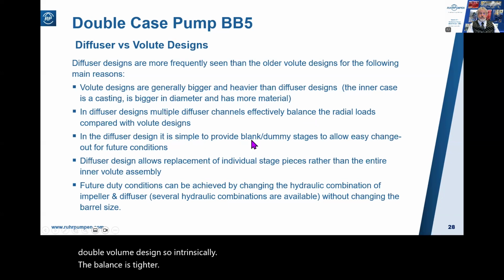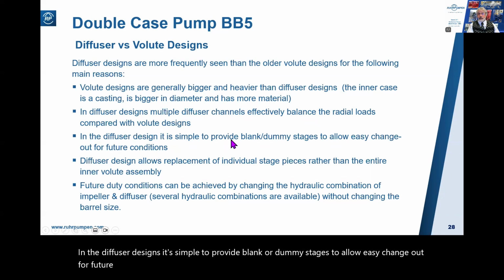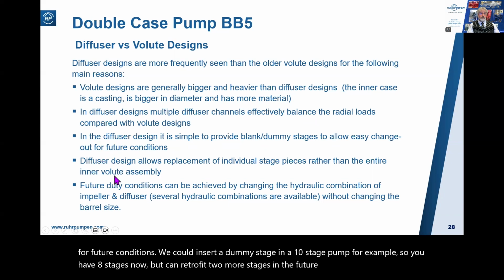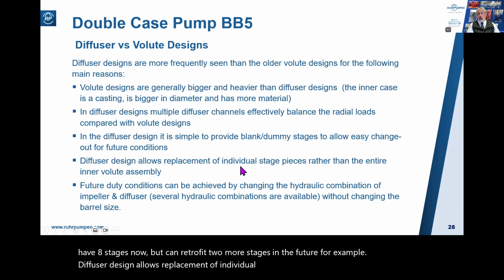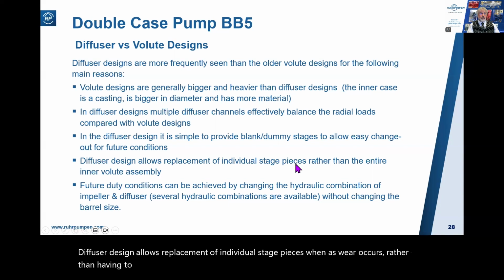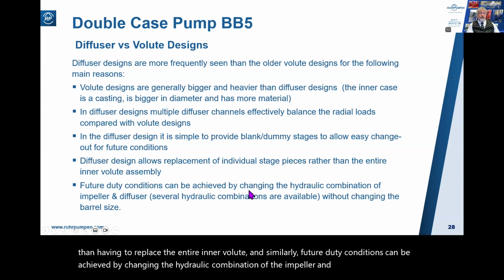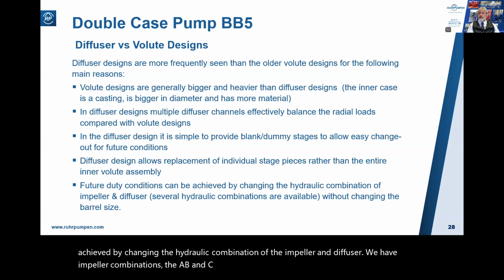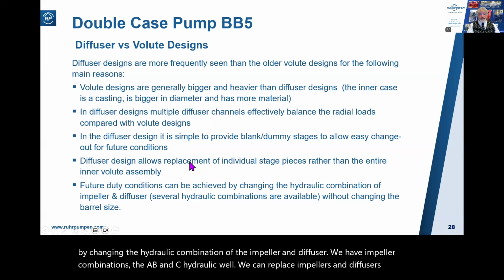In the diffuser designs, it's simple to provide blank or dummy stages to allow easy change out for future conditions. We could insert a dummy stage in a 10-stage pump, for example, so you have 8 stages now, but can retrofit 2 more stages in the future. Diffuser design allows replacement of individual stage pieces as wear occurs, rather than having to replace the entire inner volute. And similarly, future duty conditions can be achieved by changing the hydraulic combination of the impeller and diffuser. We have impeller combinations, the A, B, and C hydraulic. Well, we can replace impellers and diffusers inside an existing barrel.